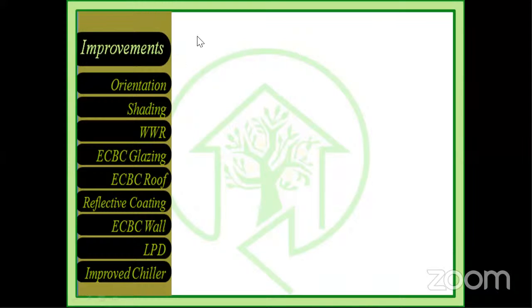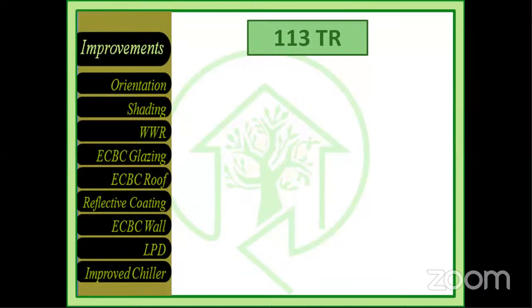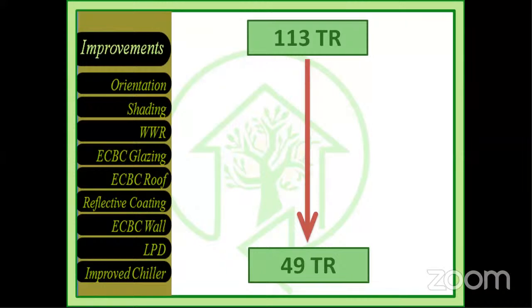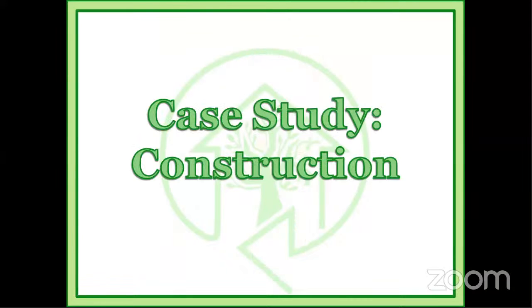Initially, when the building came to us, its cooling load was 113 tons of refrigeration. With these improvements, it reduced down to 49 TR. So we reduced this in the design stage only, I'm talking about the design stage only. In the design stage, we reduced more than 50% of the cooling load by doing these improvements. So this was the case study from the energy point of view.